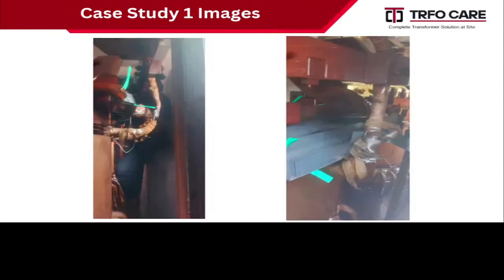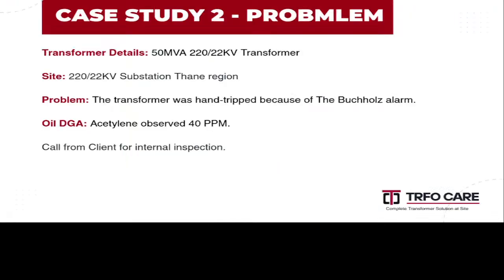See, these are the core shunts. The core shunt touches the HV winding lead, the HV bushing lead, so a spark was observed over there. We repaired it at site and this transformer is running successfully. Just because the core bindings touched the HV bushing lead, that problem occurred. We rectified it at site and this transformer has been running for around 1 year.